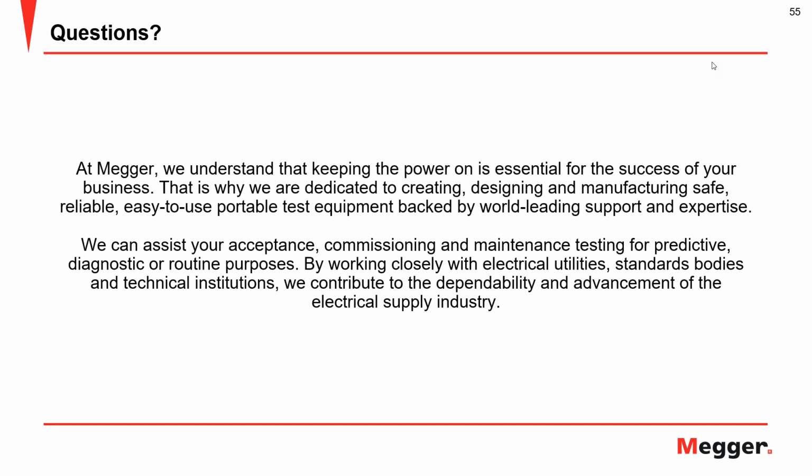Okay, that's a very broad question. When we're talking withstand testing, because this is cable testing, there has been a paradigm change over the past few decades away from DC to AC. Typical power cables, you test with AC.